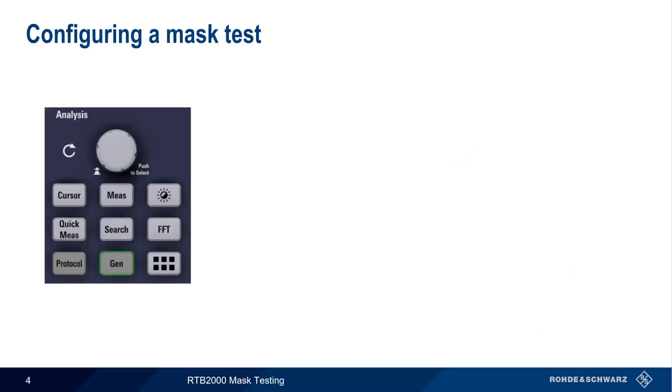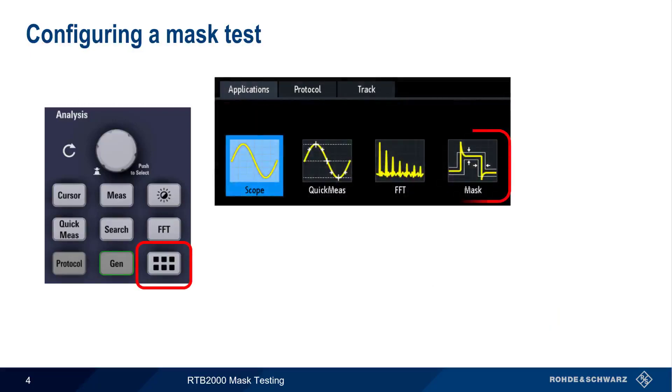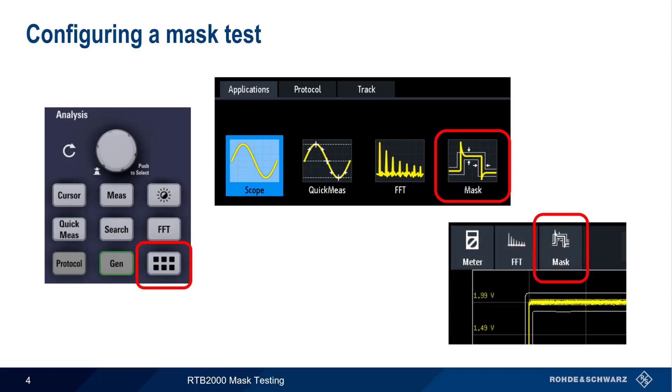To configure a mask test, first press the Applications hard key on the front of the RTB, and then select Mask from the list of available applications. Mask testing can also be started using the Mask icon in the toolbar menu.